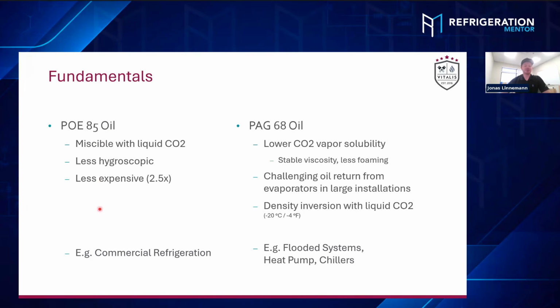The POE oil is very commonly used in normal refrigeration, either commercial but also industrial. It's a little less hygroscopic. That means the oil itself doesn't saturate that much with humidity out of the air, but still you don't want to have the oil just sitting there open to the environment, right? And the miscibility with liquid CO2 is definitely a good point because the POE oil is mostly dissolving completely within the liquid CO2. That's totally different to the PAG oil, actually.